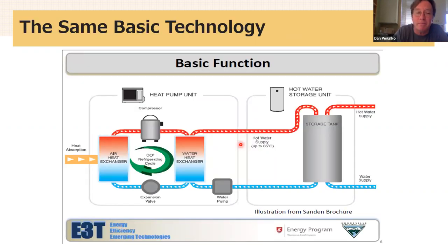This is another diagram of the heat pump system. This is from a split system. So it's laid out like there's a tank inside and a heat pump outside. And from the perspective of how the system works, it really doesn't matter if one piece is outside, one piece is inside, or whether they're stacked on top of each other. What you have going on here is refrigerant boiling off and absorbing heat from the outside air. And so that's air to refrigerant heat exchange. And then here in that heat exchanger I told you drops down into the tank, you have the vapor condensing and releasing heat to the water. So you have refrigerant to water heat exchange. And so in the split system, there's water plumbing between the tank and the heat pump. In the unitary systems, they're all one unit and they're sort of stuck together.